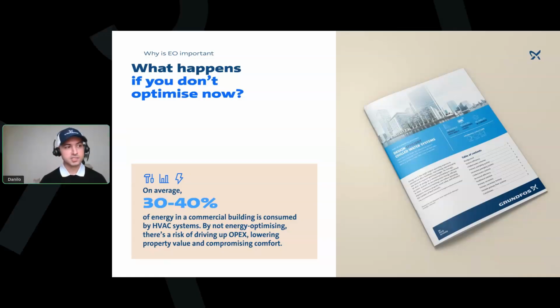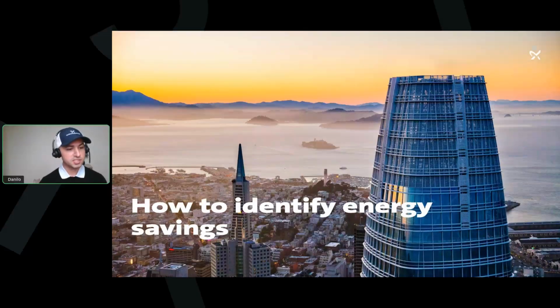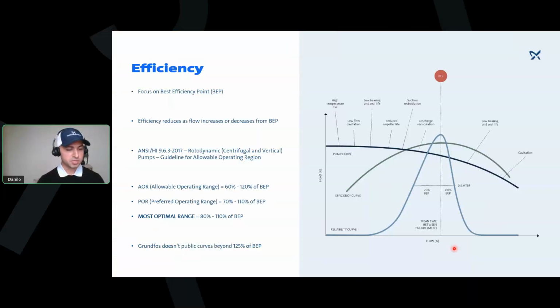So moving on, this completes why energy optimization is important. Now, next is how do we identify energy savings? Let's start with efficiency, so let's start with pump curves. Once again, we're looking at pump curves. We don't talk about pumps without looking at pump curves. I'll start on the right side. You see three curves. The dark blue one is the pump curve, the green one is the efficiency curve, and the light blue one is the reliability curve. We'll go one by one, starting with the pump curve.